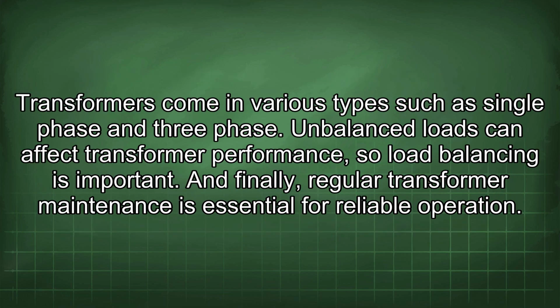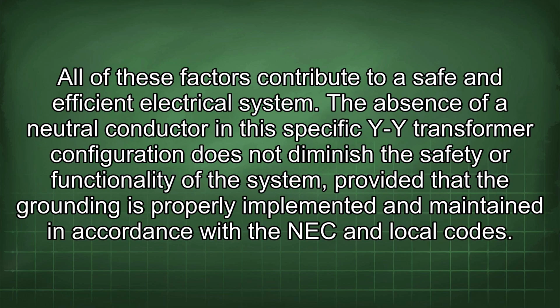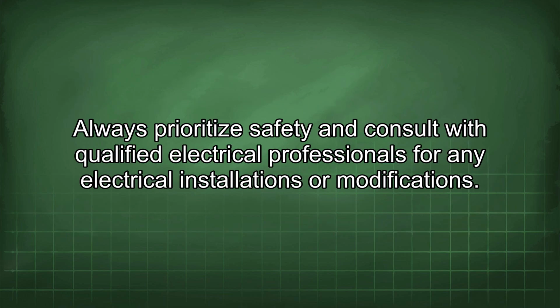Transformers come in various types such as single-phase and 3-phase. Unbalanced loads can affect transformer performance, so load balancing is important. And finally, regular transformer maintenance is essential for reliable operation. All of these factors contribute to a safe and efficient electrical system. The absence of a neutral conductor in this specific YY transformer configuration does not diminish the safety or functionality of the system, provided that the grounding is properly implemented and maintained in accordance with the NEC and local codes. Always prioritize safety and consult with qualified electrical professionals for any electrical installations or modifications.